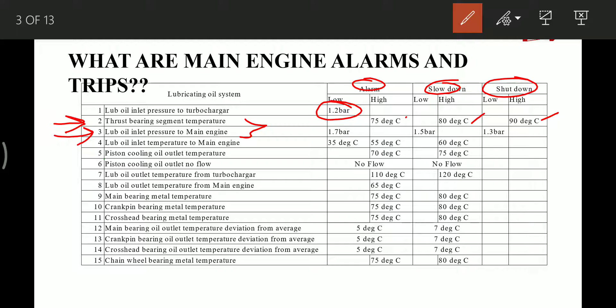Lube oil inlet temperature to main engine: at 35°C it gives a low temperature alarm and at 55°C it gives a high temperature alarm. At 60°C it slows down the main engine. Piston cooling oil outlet no-flow gives a no-flow alarm and also slows down the engine. Lube oil outlet temperature from turbocharger: high alarm at 110°C and slowdown at 120°C.